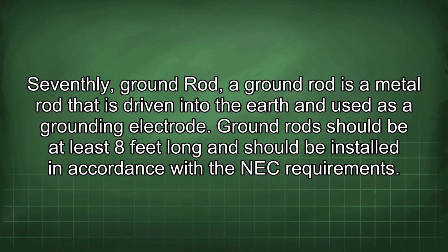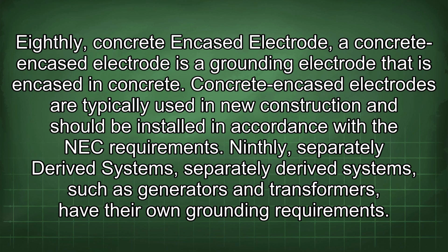Seventhly, ground rod. A ground rod is a metal rod that is driven into the earth and used as a grounding electrode. Ground rods should be at least 8 feet long and should be installed in accordance with the NEC requirements. Eighthly, concrete encased electrode. A concrete encased electrode is a grounding electrode that is encased in concrete. Concrete encased electrodes are typically used in new construction and should be installed in accordance with the NEC requirements.